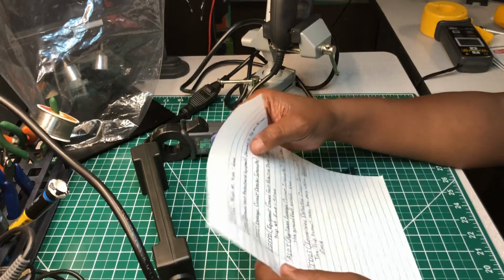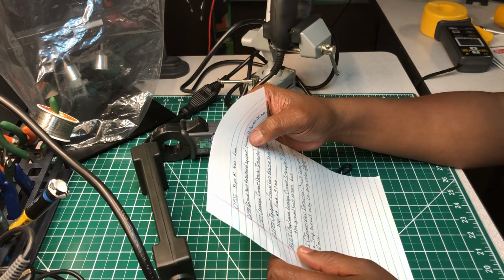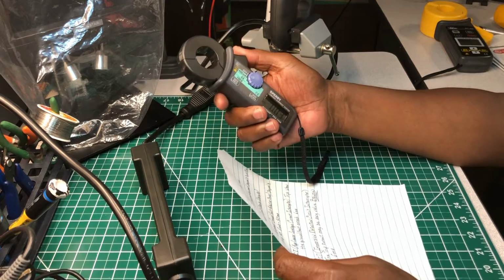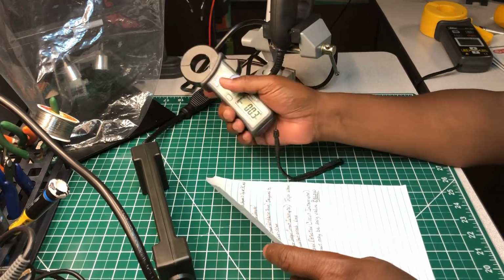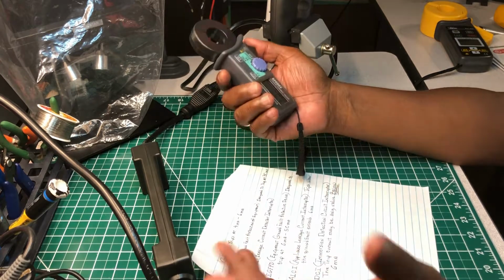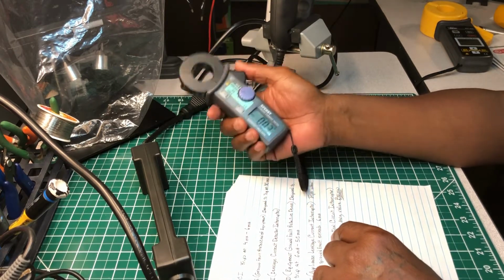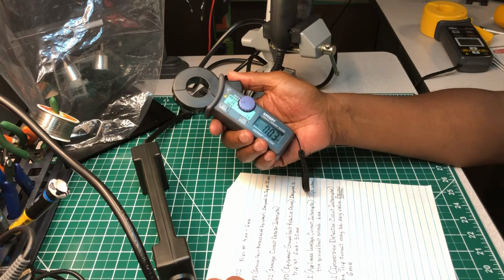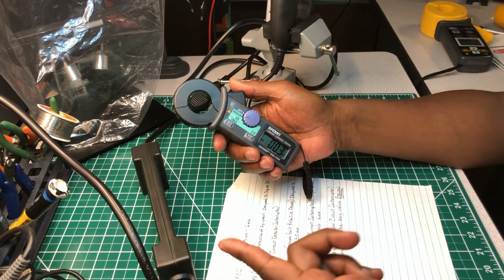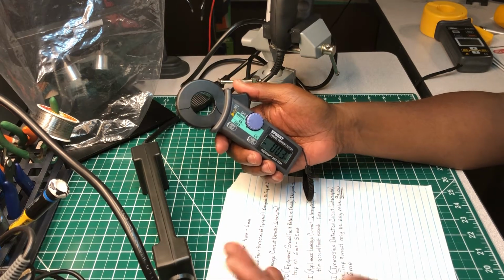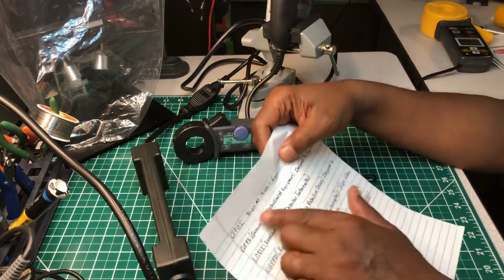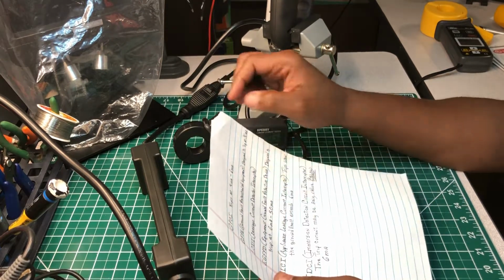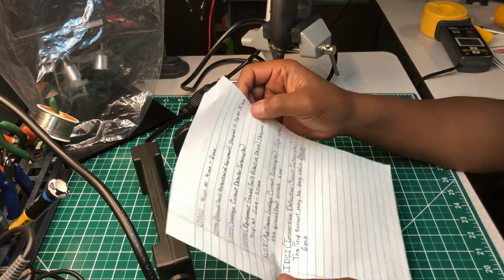The GFCI, which stands for ground fault circuit interrupter, trips at 4 milliamps to 6 milliamps. And if you plug this in and take a reading and you're getting 8 milliamps, well, that's your reason why it's tripping that circuit breaker. The GFCI is working properly, it's doing what it's supposed to do because the reading is out of its range. That's what trips it, between 4 and 6 milliamps.